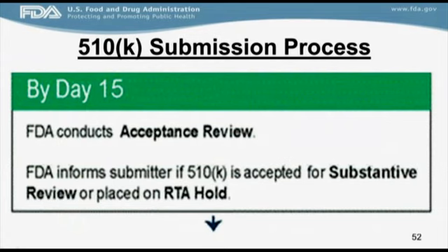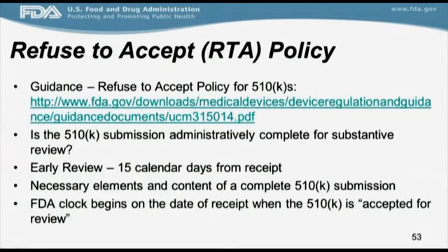By day 15, after your 510K has passed through the user fee and e-copy, the FDA will conduct what's called an acceptance review. By day 15, you will find out from the FDA if your 510K has been accepted for substantive review or if it has been placed on refuse to accept hold. The refuse to accept policy is outlined in the guidance and the link provided on this slide. I recommend that you review that guidance thoroughly.